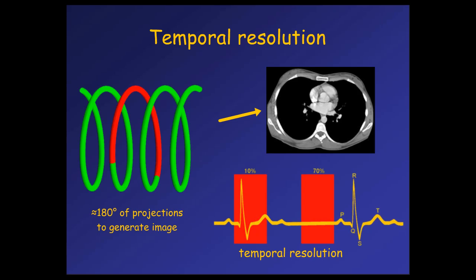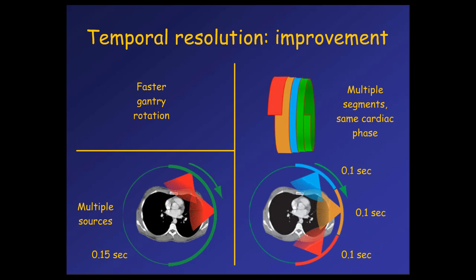What can we do about that? There's different ways to improve temporal resolution on the images. First of all, you can make the gantry rotate faster. The problem is that right now the gantry weighs several thousand pounds, and we're getting close to reaching the engineering limitations of making that thing rotate as fast as possible. In the later scanners, we'll see very small improvements in gantry rotation speed. Another way that we can use to improve temporal resolution is as follows. Given that the helical data set is highly overlapped, what we can do instead of taking half a rotation worth of projection...